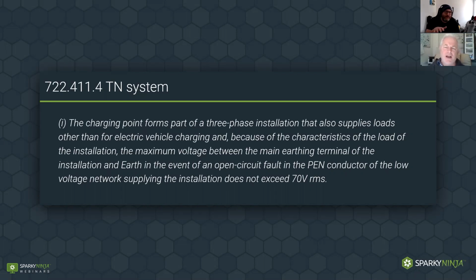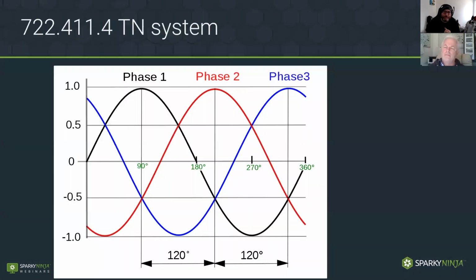I was just going to say that. Yeah, it's almost an impossibility, because even if you balance it on paper, as loads switch on and switch off on your system, your phases are going to become unbalanced. So it's almost an impossibility, unless you're supplying just one piece of equipment, a three-phase motor. Yeah. The science works, the theory works, but the practicality of this is just a non-starter for most. And everyone kind of goes past this one.